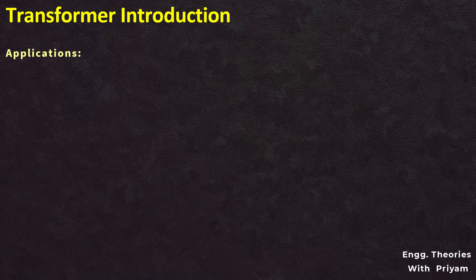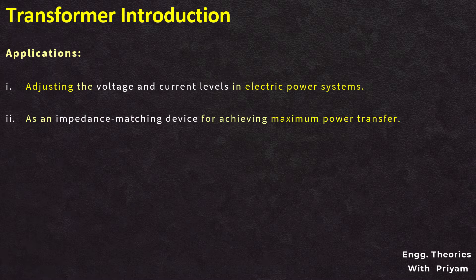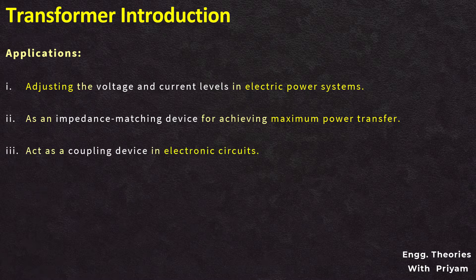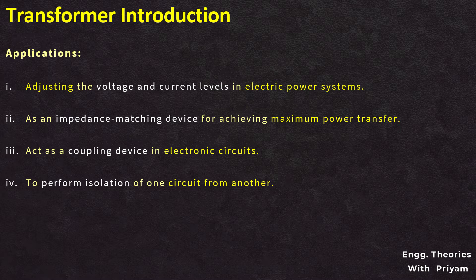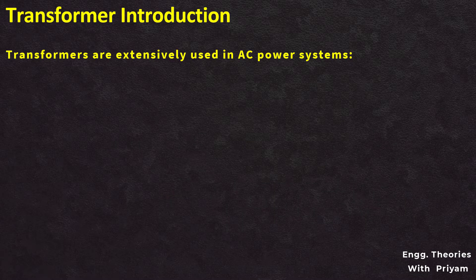The major uses of an electrical transformer include: adjusting voltage and current levels in electric power systems; acting as an impedance matching device for achieving maximum power transfer in low-power electrical and control circuits; acting as a coupling device in electronic circuits; and performing the isolation of one circuit from another, since the primary and secondary of the transformer are not electrically connected. Transformers are also used for voltage and current measurements — these are known as instrument transformers.